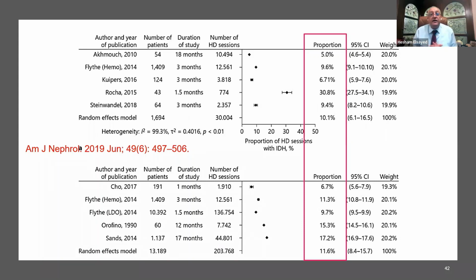If you find that many patients require intervention for intradialytic hypotension, you have to check your water treatment stations, the conductivity meters on the hemodialysis machines, and the others. If you find a single patient has very frequent intradialytic hypotension, exclude pericardial tamponade, cardiovascular diseases, malnutrition, inflammation, septicemia, catheter problems, and even pulmonary issues.